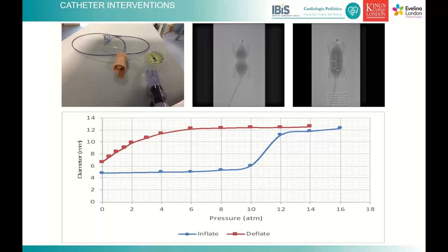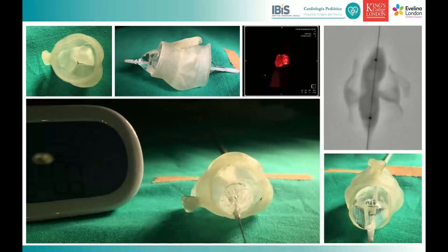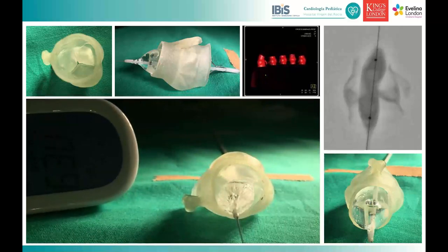For pulmonary arteries, we simulated balloon dilatation of a stenotic pulmonary artery using a high-pressure balloon to open it up to three times. With the right thickness — 0.4 mm of polyurethane — we could inflate the balloon to nominal pressure without bursting the model, replicating the same specifications used for patient balloons. For valvuloplasty and valve tissue, we used a different material called Tango, allowing simulation of aortic valve stenosis dilation with a low-pressure balloon.